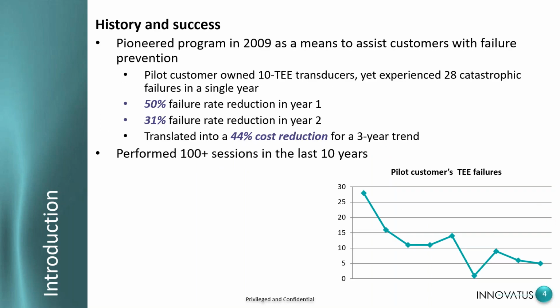So we did pilot this program in 2009. This one pilot customer, and this is just a single example, just to show you folks some of the data, but we had one customer who had 10 TEE probes, but yet had 28 catastrophic failures in a single year. So almost 3 catastrophic failures per 1 TE probe that they owned. We were able to cut that in half in year 1 and then an additional 31% in year 2, which translates to a 44% cost reduction for a 3-year trend. So obviously today, hospitals are being squeezed tighter and tighter on their budgets.